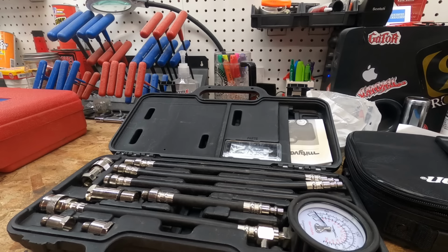If it's under the 90, 80 PSI mark, I'll call the customer up and say, hey, look, here's where we're at. These things like to run on at least 100 PSI. Do you want me to dig further and see what the issue is? Most of the time it's going to be A, B, C, or D. Here's the estimated cost. And from there, they'll say, oh, heck no, I can buy a new unit for $150. I'll just go do that.